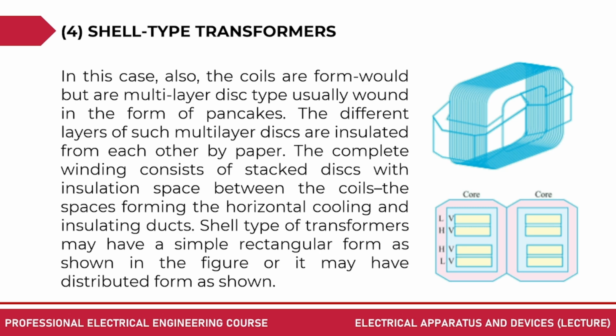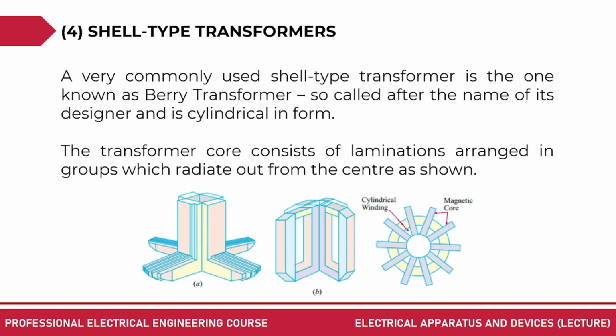Not last, but the other form, the other type. Okay, so we have another type of transformer. For shell type, in this case also the coils are form wound but are multi-layered discs, usually wound in the form of pancakes. The different layers of such multi-layer discs are insulated from each other by paper. Okay, that's for the shell type. The complete winding consists of stacked discs with insulation space between the coils, the spaces forming the horizontal cooling and insulating ducts. Shell type transformers may have a simple rectangular form as shown in the figure, or it may have distributed form as shown.